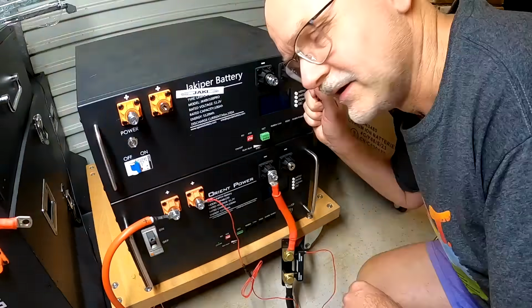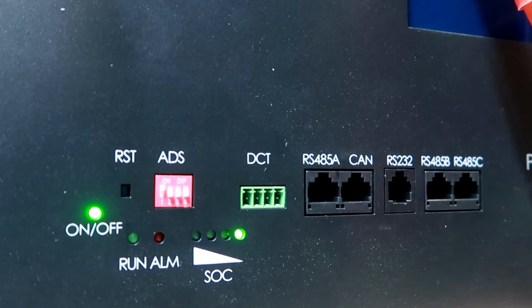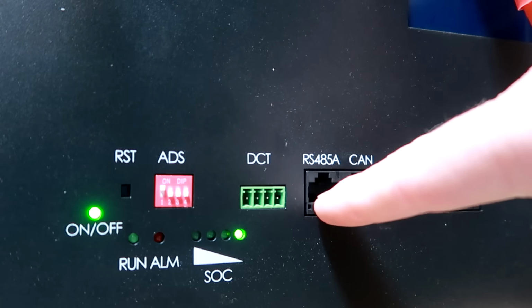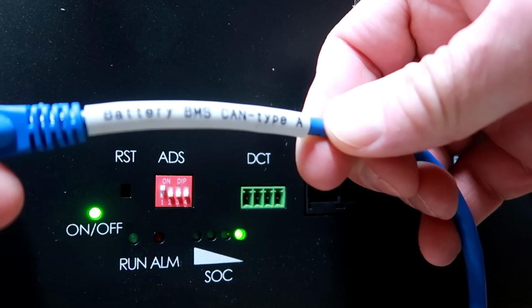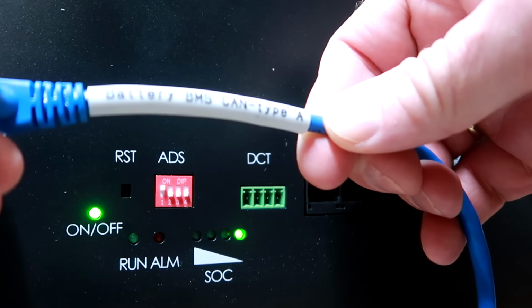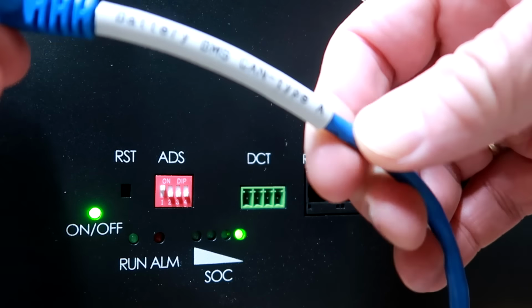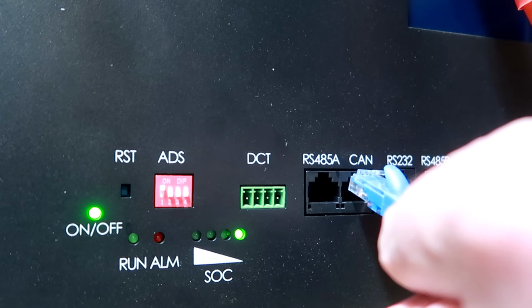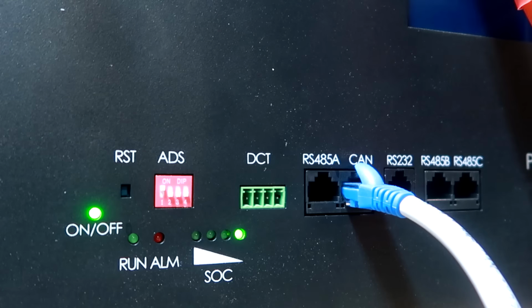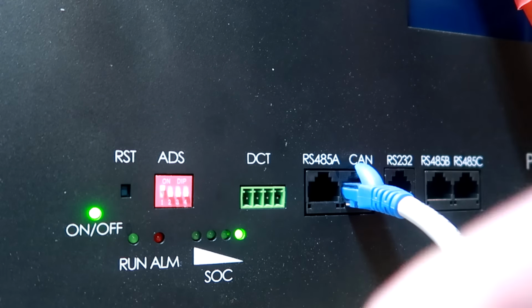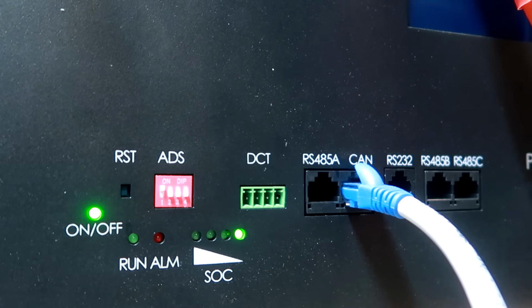And then we obviously have to connect the master battery via CAN to our inverter or Victron system in this case, or if you have an RS485 connection to your inverter. So we are using the usual battery BMS CAN Type A cable from Victron. I'll link this down below. And we plug this into our CAN port here on the master battery, and the other end goes to our Victron system, either the Raspberry Pi with a CAN head or the Cerbo GX, directly to the BMS CAN bus.